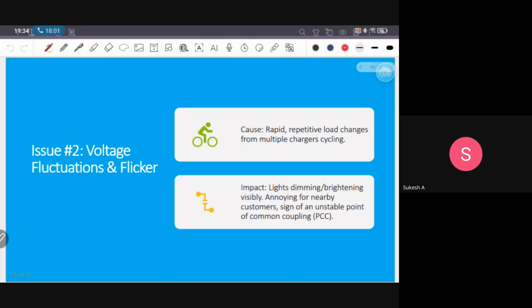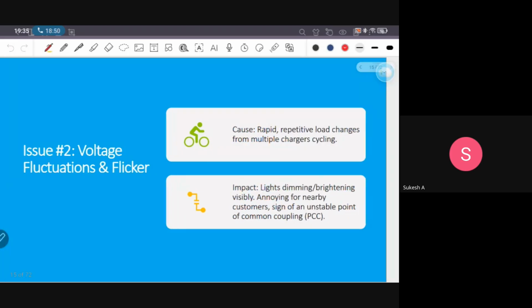And in a charging plaza, that is a charging station, multiple chargers cycle on and off independently as vehicles finish charging. This creates rapid, repetitive, small changes in total load. The result is continuous, maddening fluctuation in voltage, visible as lights that dim and brighten rhythmically. Because the power curve never experienced such ripples or such spikes in the recent era, we are facing very rapid, unrhythmic flickers and fluctuations in power demand that cause voltage fluctuations and flicker.